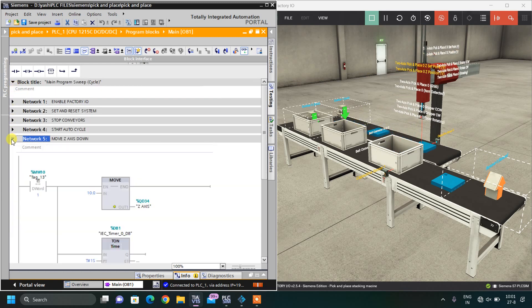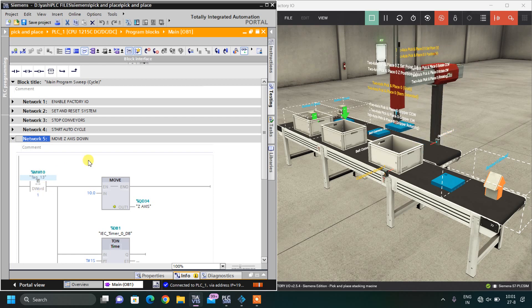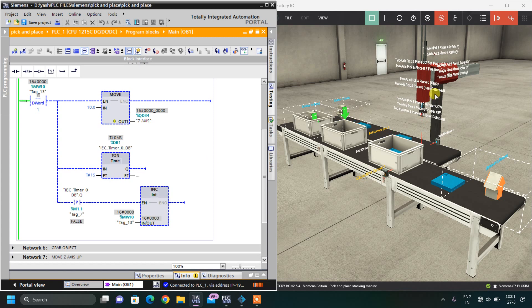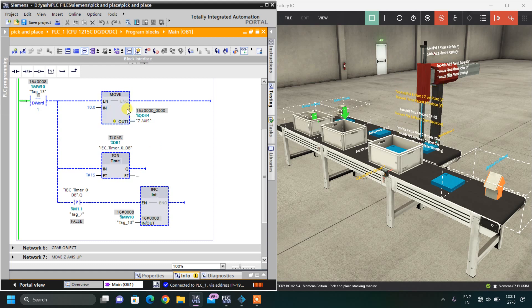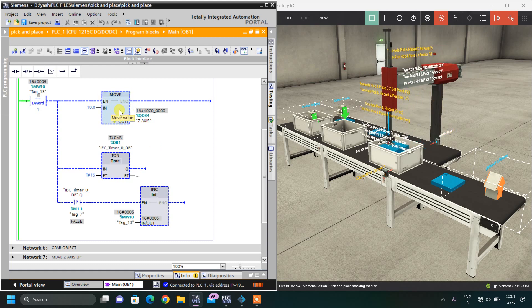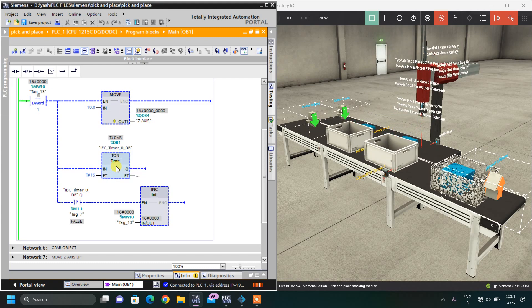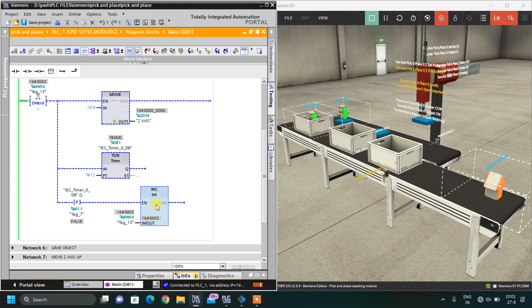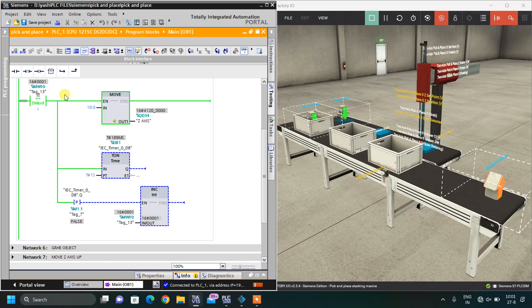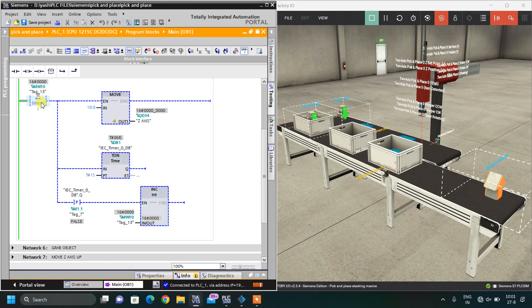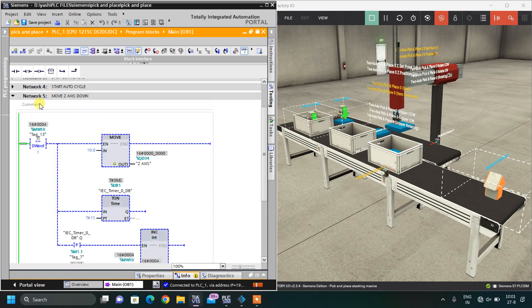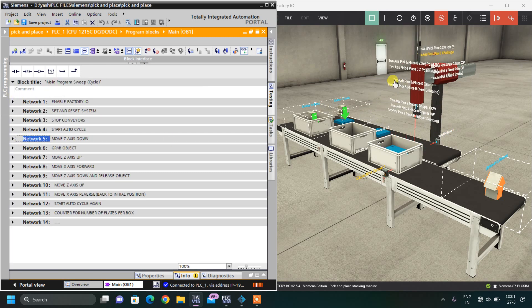When the memory word value is 1, that is step 1: Z axis should move to 10. After some time delay it will increment MW10 by 1, completing step 1. When the first step is complete and after a 1-second delay, I increase the memory bit to initiate step 2. The Z axis moves down, then the memory bit increments so this condition becomes false and won't trigger again.